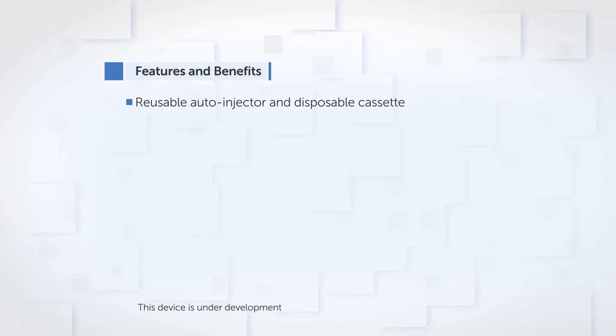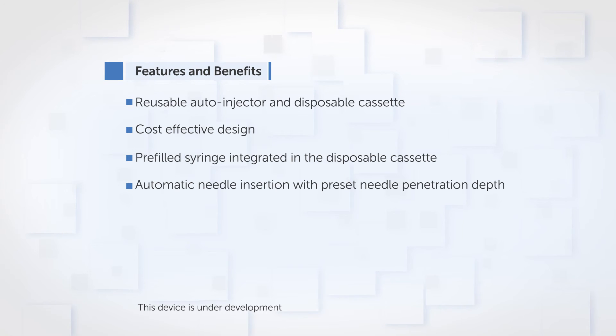Features and benefits: reusable auto-injector and disposable cassette, cost-effective design, pre-filled syringe integrated in the disposable cassette, automatic needle insertion with preset needle penetration depth, automatic injection with preset injection speed, and full needle protection.